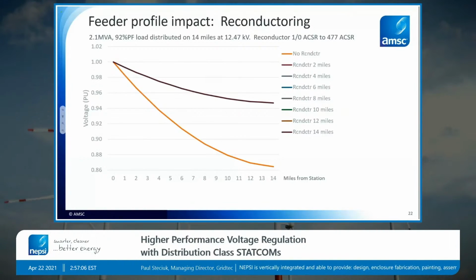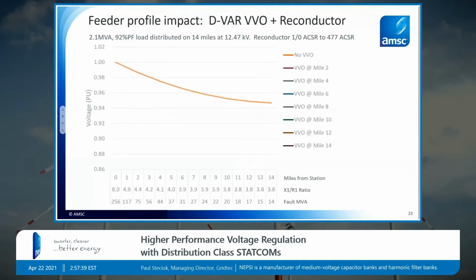And this is why we sometimes say that the VVO has the effect of stiffening the circuit, exactly for this reason. And then this is why when I went through the applications, we're able to use the VVO in lieu of reconductoring as a tool. From a voltage standpoint, when the problem is voltage only or power quality, the VVO becomes a much lower cost solution, much faster, much easier to install solution than having to rewire a lot of a circuit. And then just briefly, this is that same profile now if we both reconductor the feeder and use a STATCOM on that feeder. And as we can see, the STATCOM still is very effective at boosting the voltage on the feeder because it's working primarily with the inductance of that feeder.